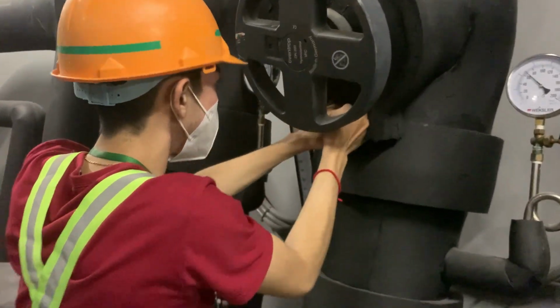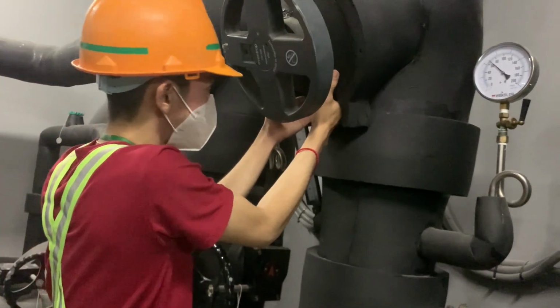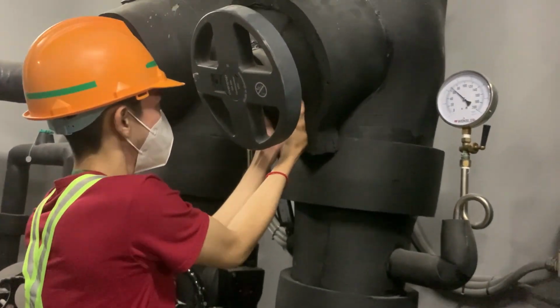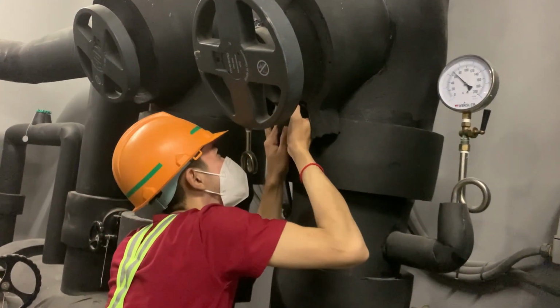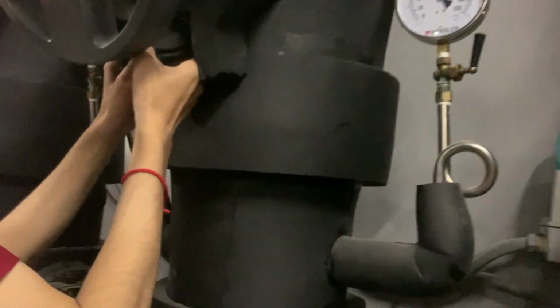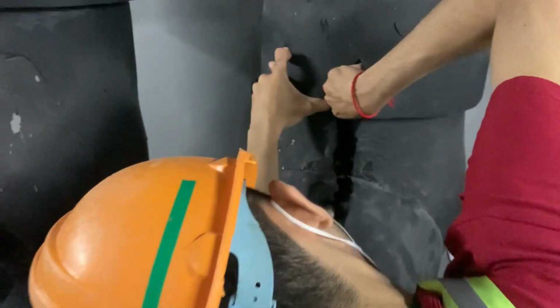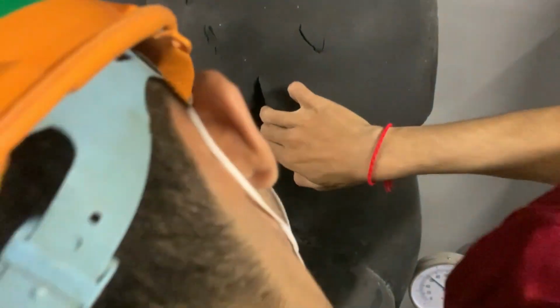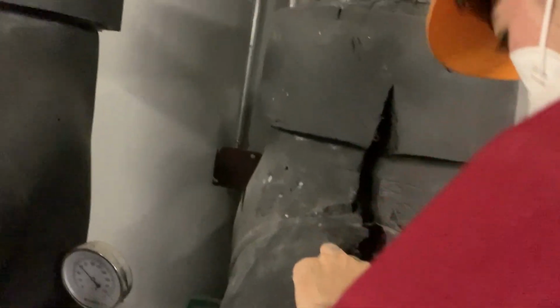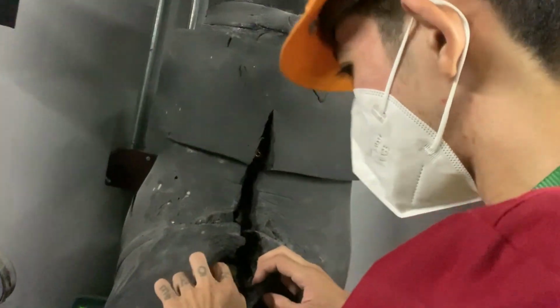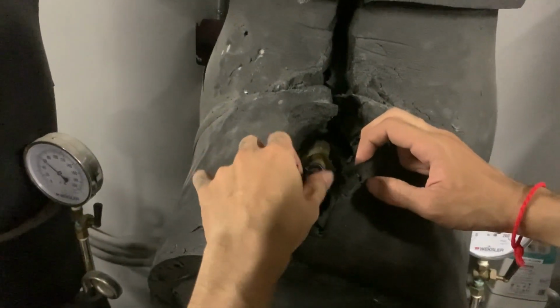Now we are having trouble with the cooling temperature of our FCUs. Here we are going to check the water flow rate of the chillers, because when the water flow is not enough, the cooling will not be enough either.